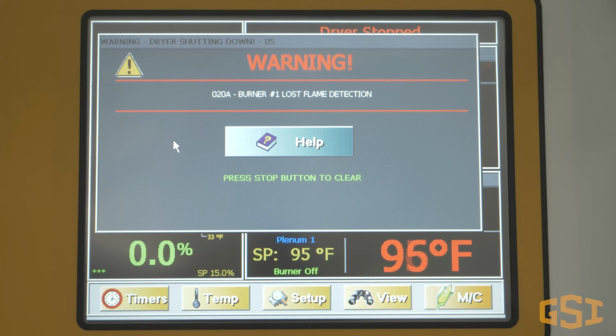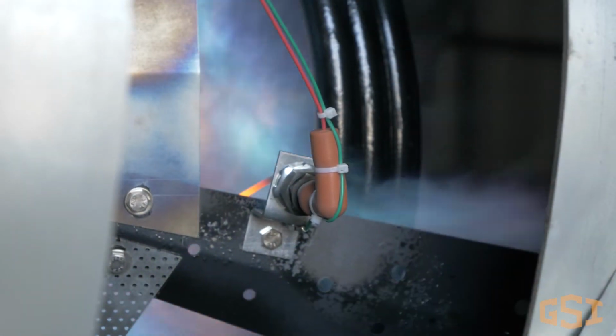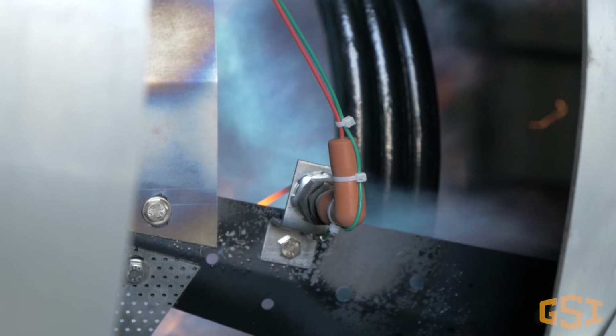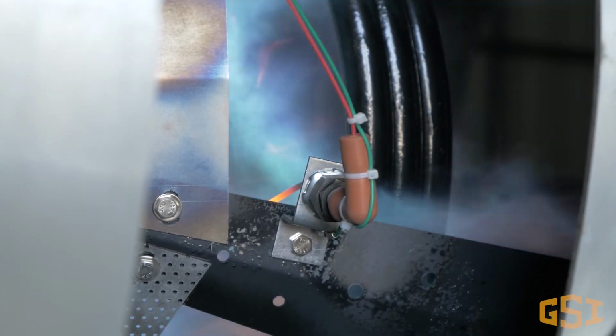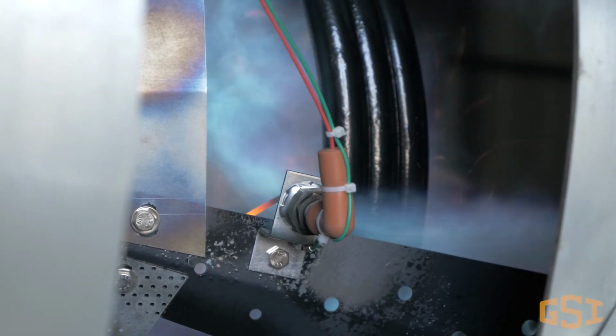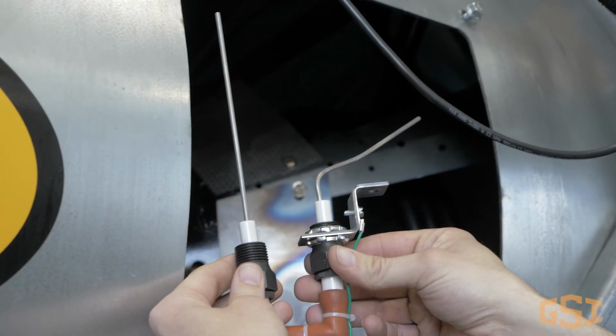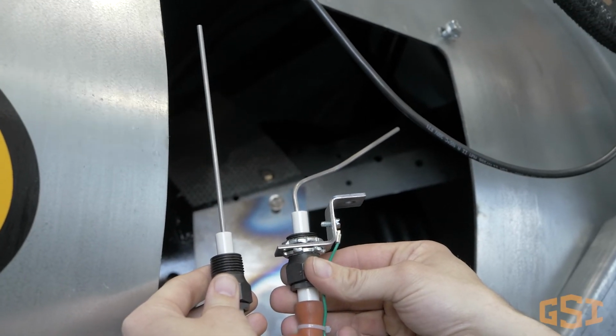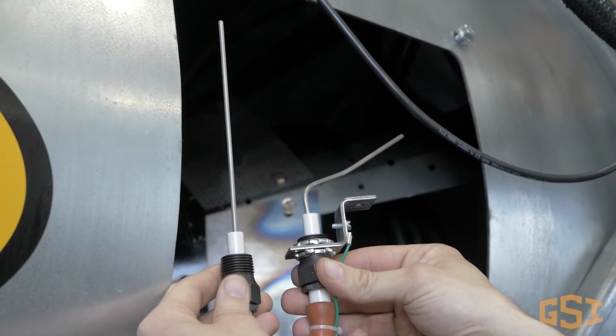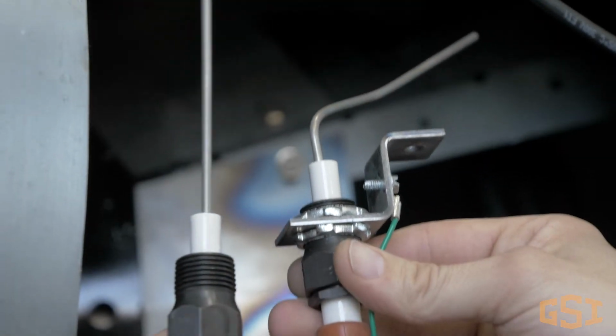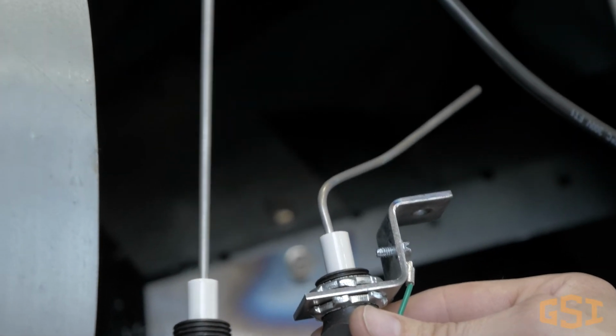Again, when the flame probe is adjusted properly, the light will always be on when the burner is on and will not blink. Now that you know how to use the burner light as a proof of flame indicator, let's discuss how to adjust the flame probe when you're having problems. Here's an image of a brand new flame probe and a flame probe installed from the factory. Notice that the flame probe is bent during installation, so the rod on the probe is located where it has the best opportunity to be in constant contact with flame.